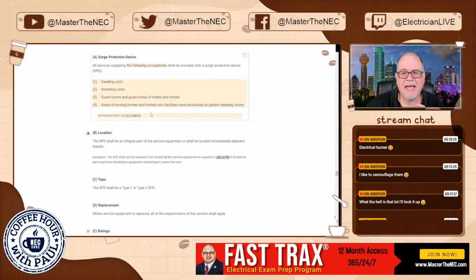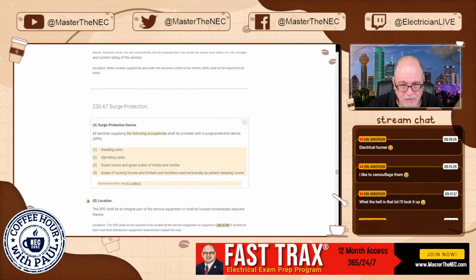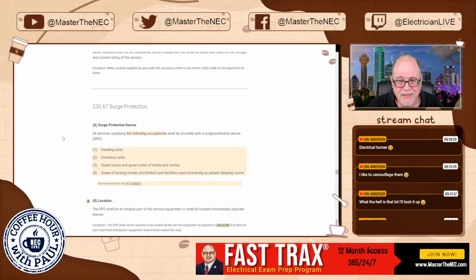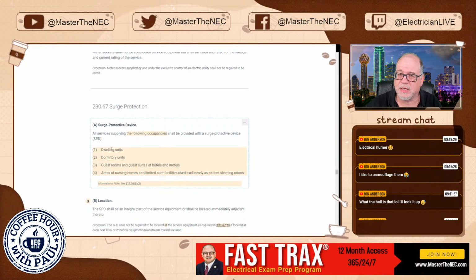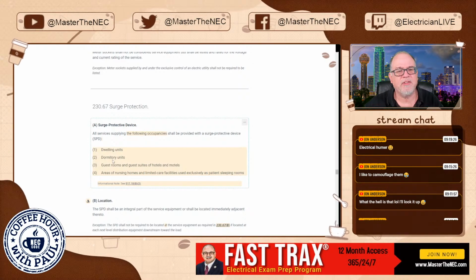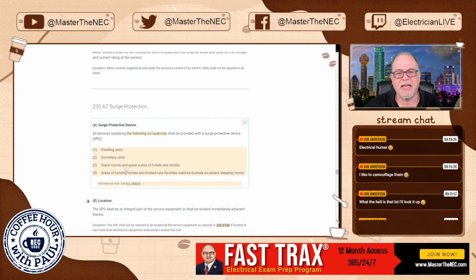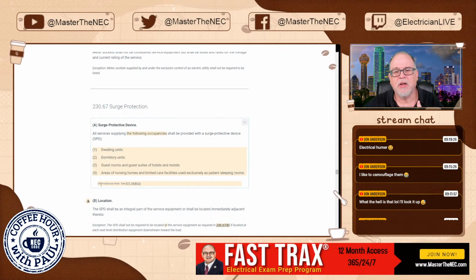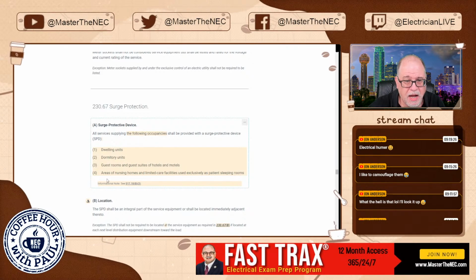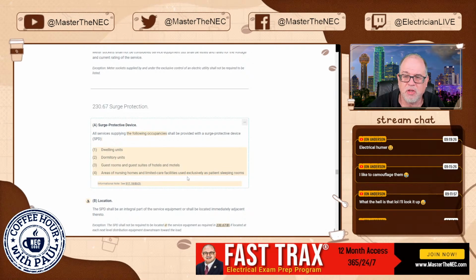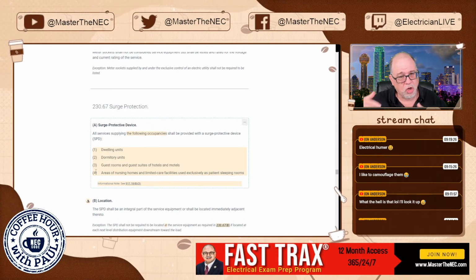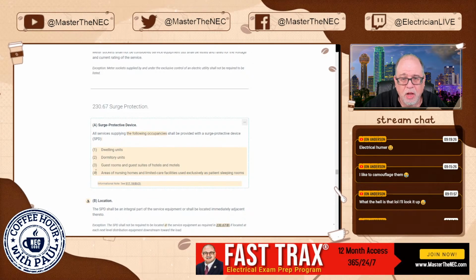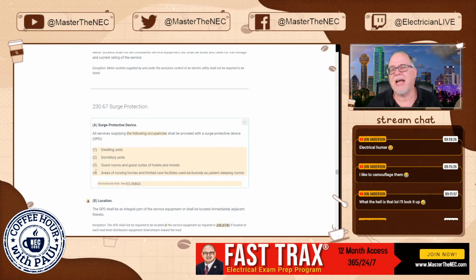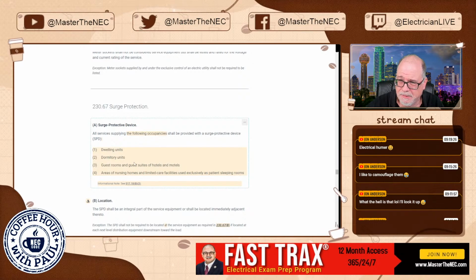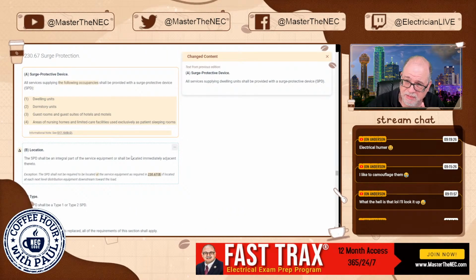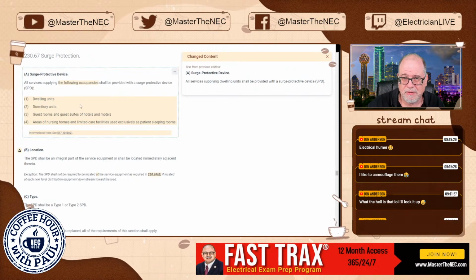Well, we've expanded this now. So services that supply dwelling units, one family dwelling, two family dwelling, that type of thing. If you have a service that's going to that dwelling unit, then you've got to have SPDs. Services to dormitory units, services to guest rooms and guest suites, hotels and motels are going to have SPDs now. Services to the following areas of nursing homes and limited care facilities used exclusively for patient sleeping rooms, those services supplying those circuits are going to have SPDs. So you had to have it previously, right? That's not new, but previously it only applied to what? Dwelling units. Now it's expanded a little bit.